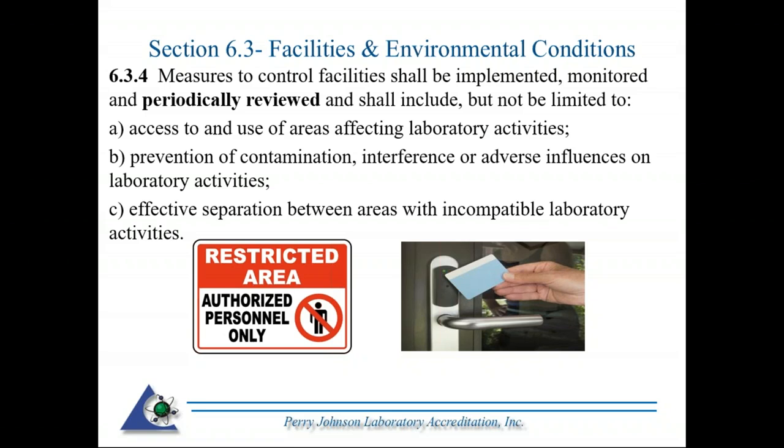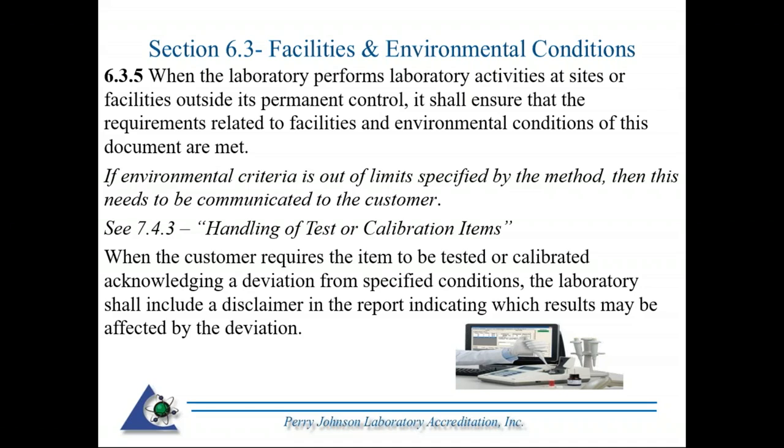So if you have a sensitive area where vibration is very susceptible to be picked up, you don't want any sort of activity that may incorporate that within that specific area of testing or calibration. Okay, so here what we were talking about, the key difference between the two standards, 2005-2017. When the laboratory performs laboratory activities at sites or facilities outside its permanent control, it shall ensure that the requirements related to facilities and environmental conditions of this document are met. So this would be, for instance, on-site calibrations.